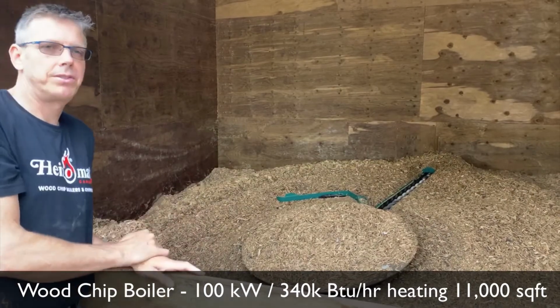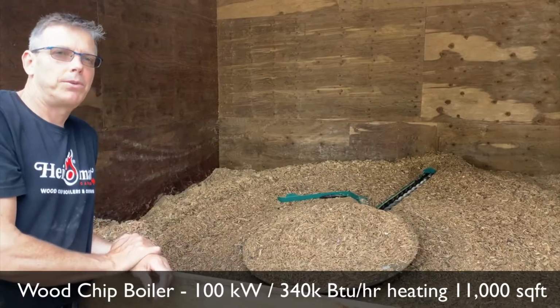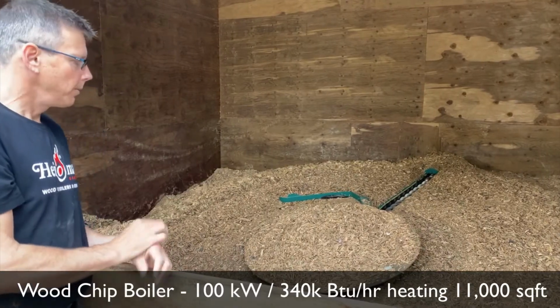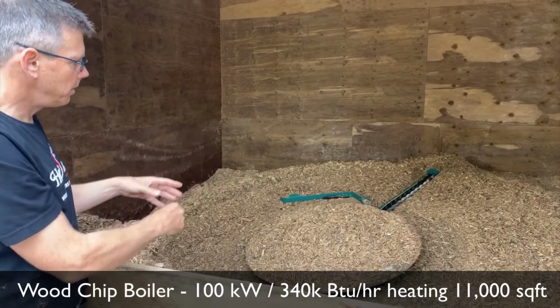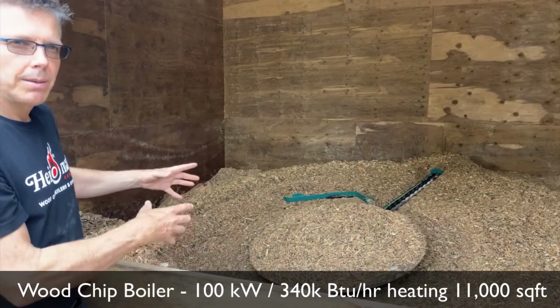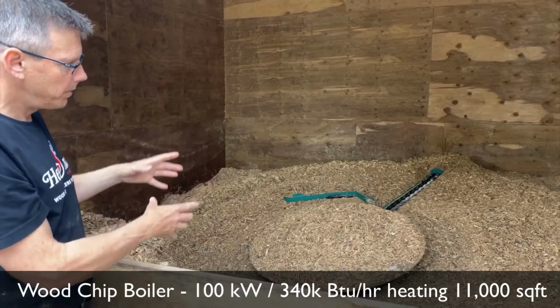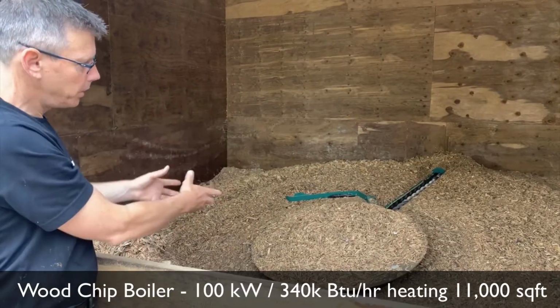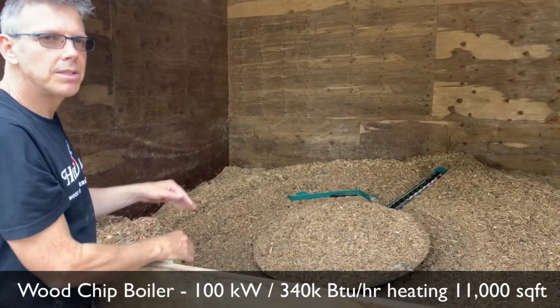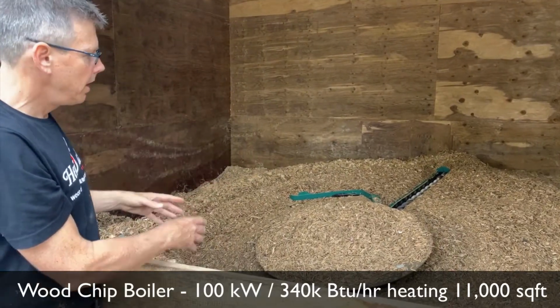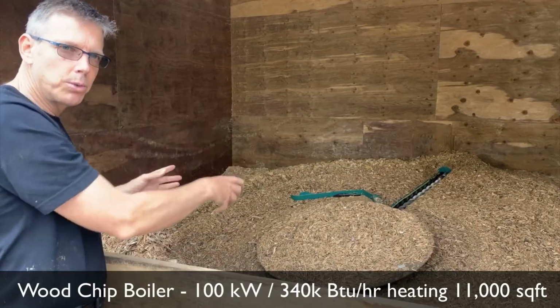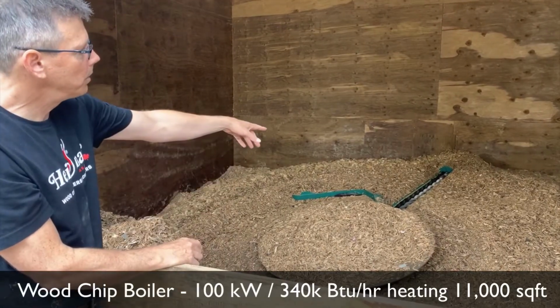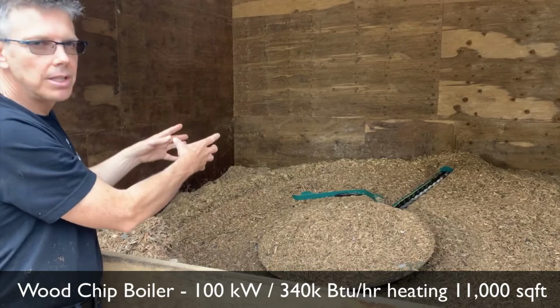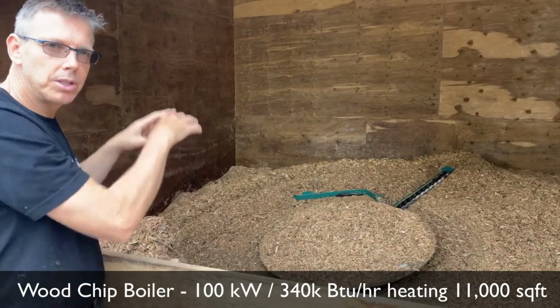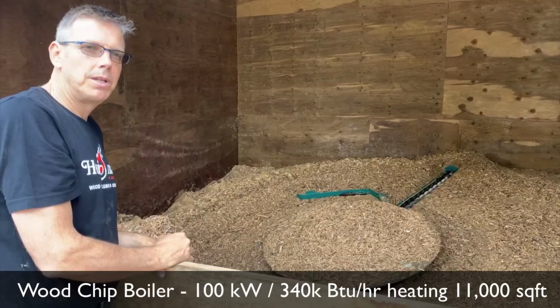This is the unloading system in the bottom of the bunker. It's not very different to a silo unloading system. There's a gearbox running these extendable arms, which are sprung so that when the bunker is full they're hidden underneath the pressure plate in the center, protecting them from the weight of the chip above. As the boiler calls for fuel, the arms rotate and drag the fuel into the open auger, taking it from the center of the bunker first. That prevents bridging of the fuel higher up and makes sure we have a nice consistent flow of fuel.